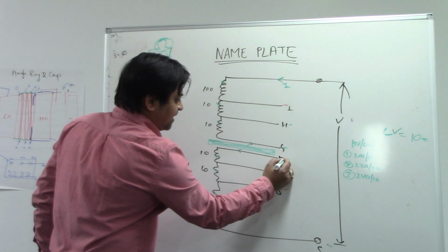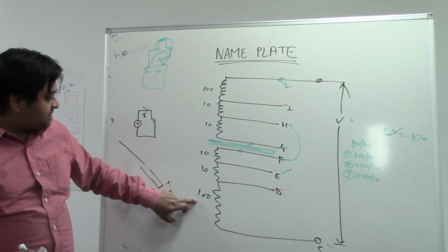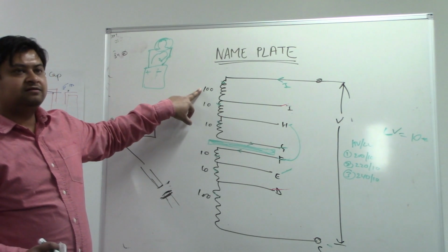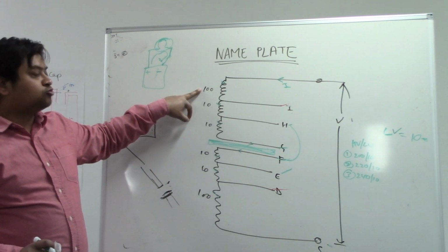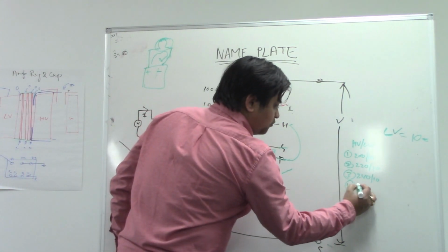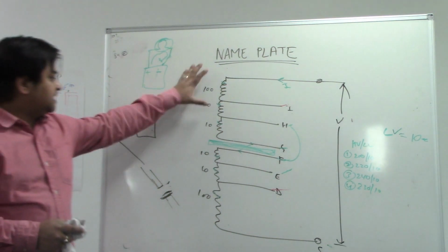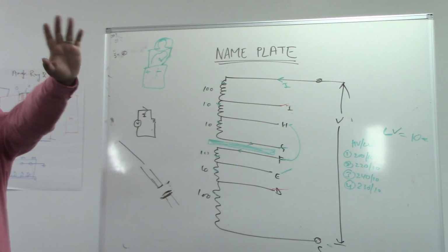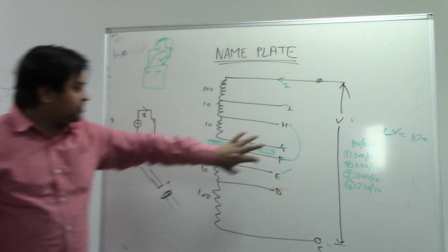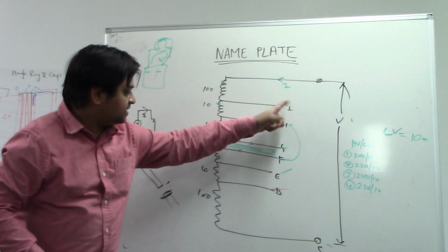Then if you go F and H, how much do you get? 10 plus 10 plus 100, right? 120 here, and here how much? 10 and 100. 110. So 230. Right? You'll get another voltage ratio as 230 is to 10, right? So now you see this coil you are making here in the HVA. Once you have a DETC with the handle, you can change your turns like this. What is the handle doing? The handle is connecting each other.